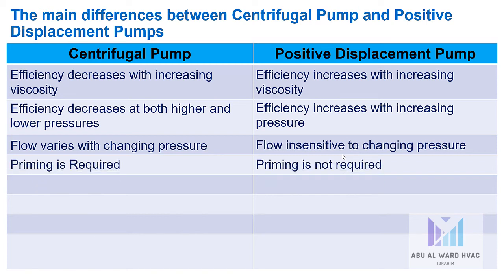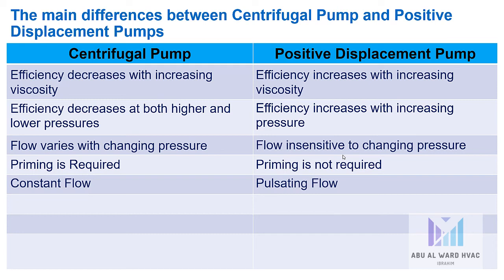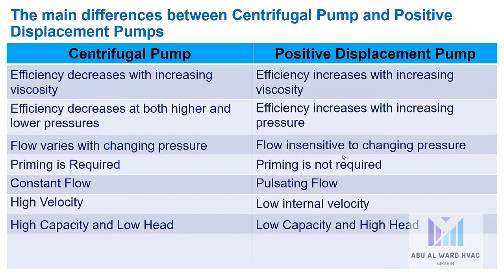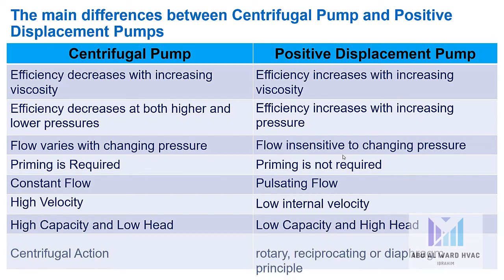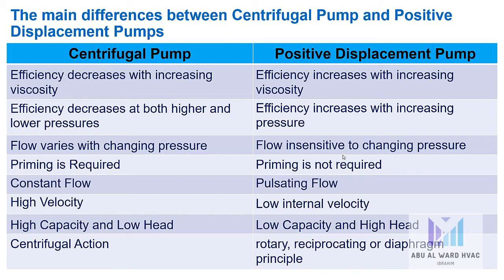Priming is required in centrifugal pumps but not in positive displacement pumps. Centrifugal pumps produce constant flow, while positive displacement pumps produce pulsating flow. Centrifugal pumps operate at higher internal velocity; positive displacement pumps at low internal velocity. Centrifugal pumps offer high capacity and low head; positive displacement pumps offer low capacity and high head. Centrifugal pumps use centrifugal action; positive displacement pumps use rotary, reciprocating, or diaphragm principles.